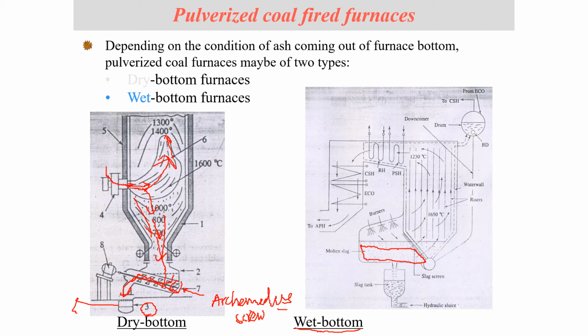So you can see that this is a fire shell kind of an arrangement. We have these water tubes in the boiler. This boiler takes in input from the economizer. As you can see, this is colder air fuel mixture, colder exhaust gas, flue gas. So we run it in the economizer. Economizer goes in the boiler, and from the boiler we go to the superheater.